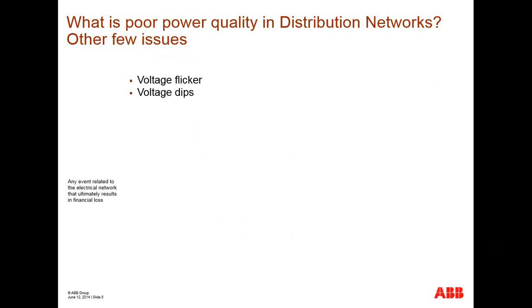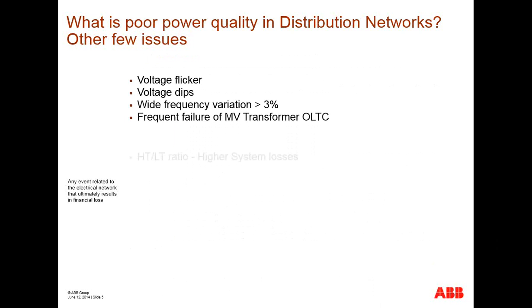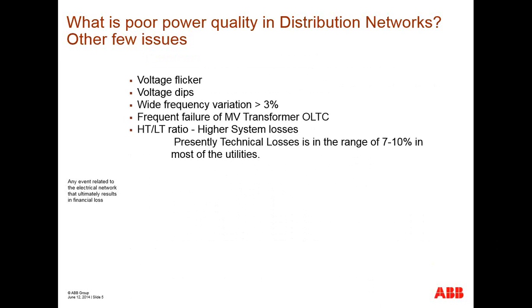Now when you talk about the other issues which are mostly seen in most of the utilities: voltage flicker, sometimes coming out from the reactive power change, voltage dip. Sometimes it is also seen as a wide range of frequency variation, frequent failure of OLTC, which is used in the transformer in order to control the voltage, because of the frequent movement. Sometimes it also causes problems. HT-LT ratio, system losses and technical losses.